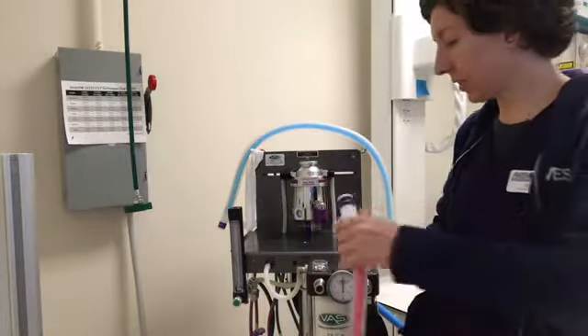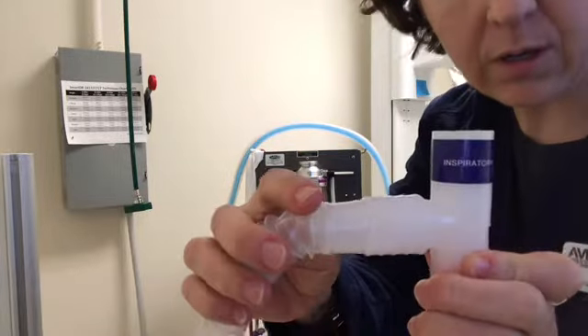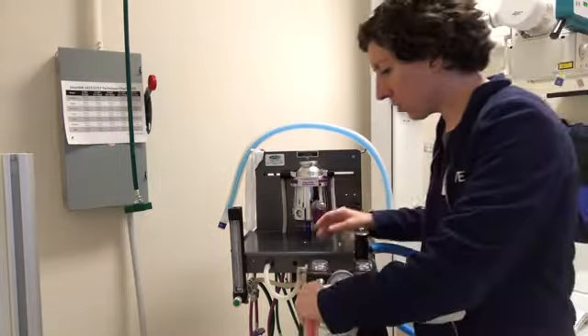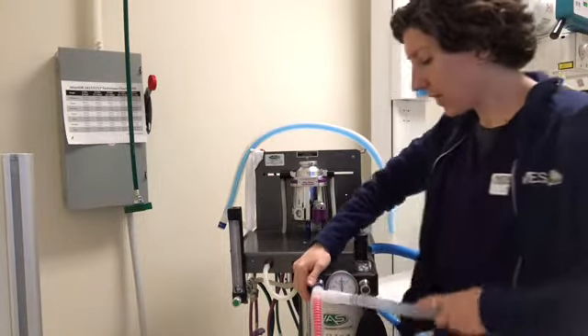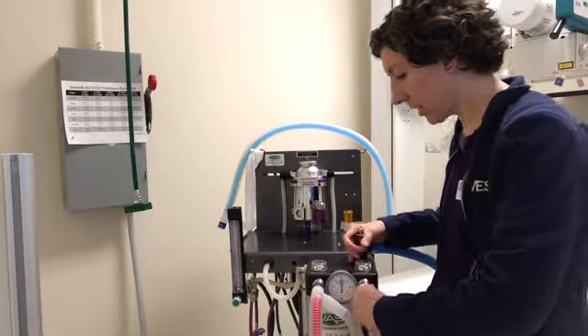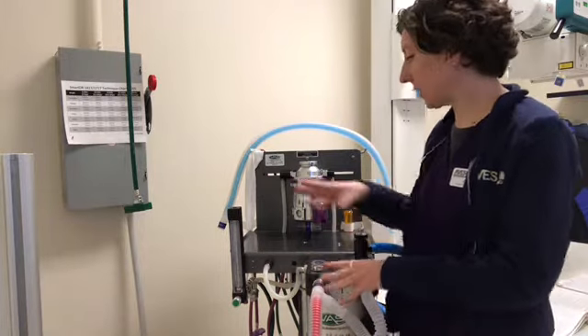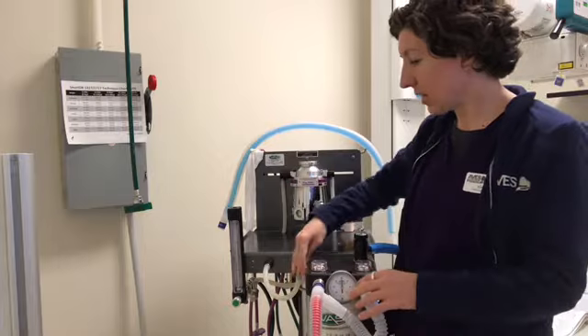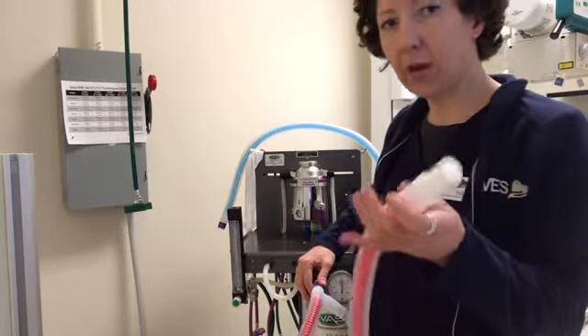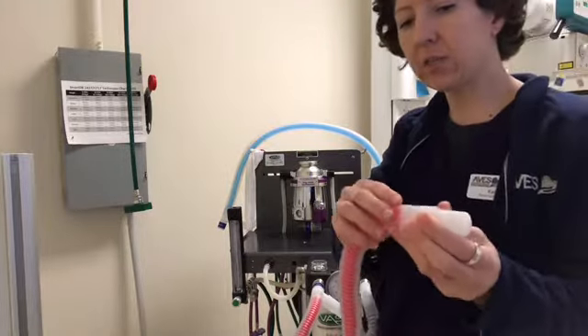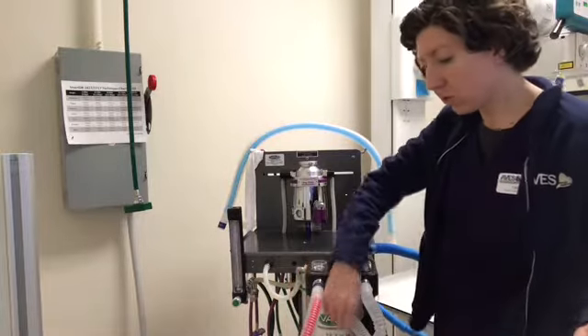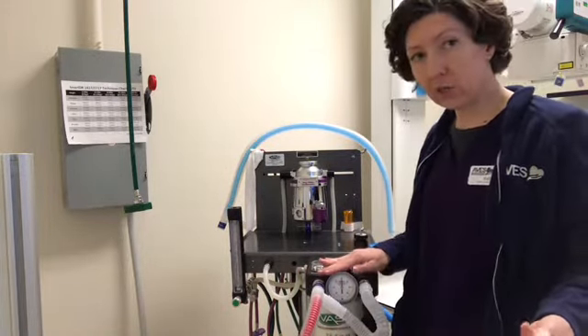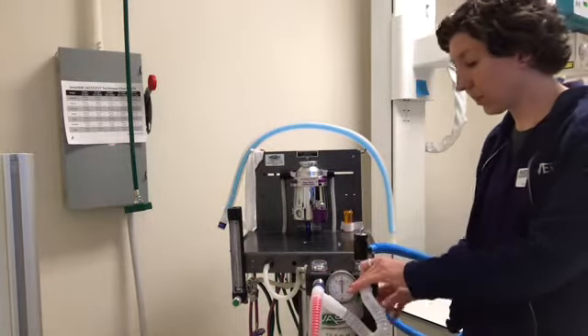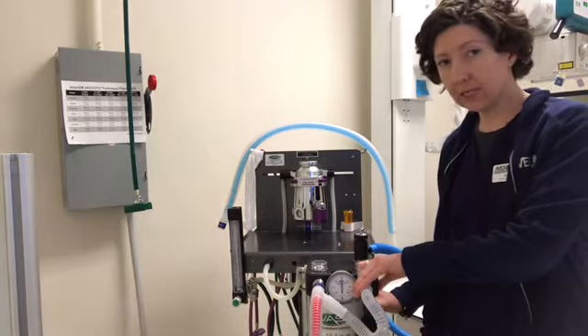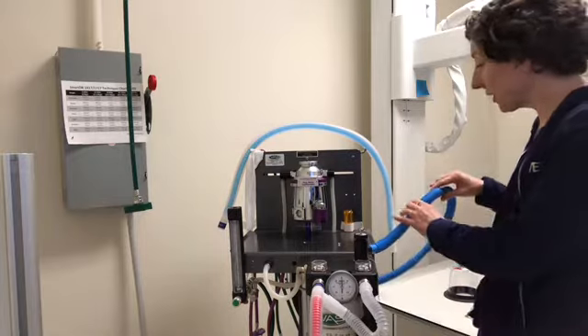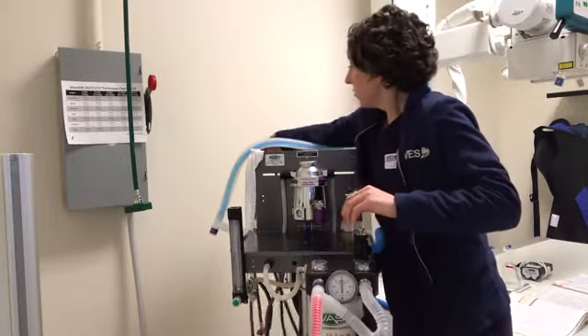So how this works is the inspiratory valve here goes into the inspiratory unidirectional valve, and then you plug this F tubing into the expiratory unidirectional valve. And so what happens is the oxygen and the anesthetic gas comes through the system, the patient takes a breath out of here, and then when they exhale, it goes into this outer tubing, and it comes back through here, goes through this Y tube into the exhalation unidirectional valve, and then it goes through the Sofnolime canister, takes away the excess CO2, and then it goes through the scavenging tubing up through.